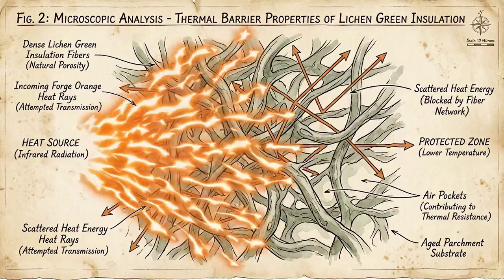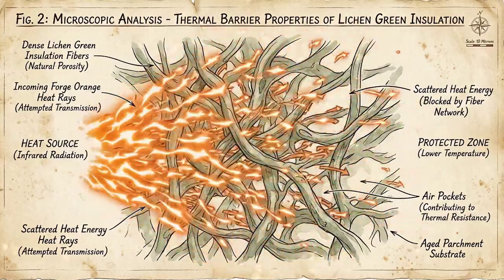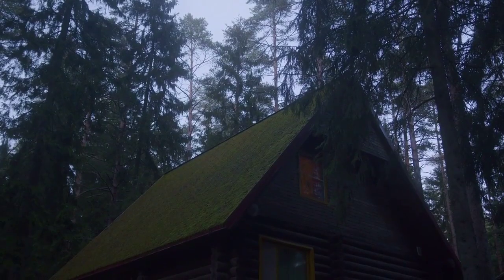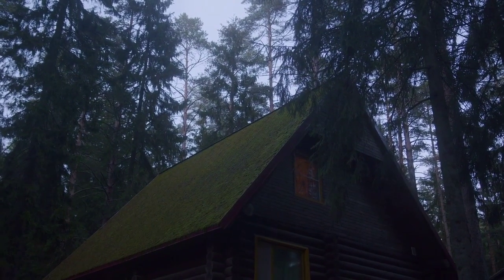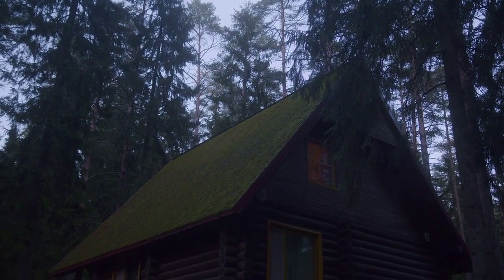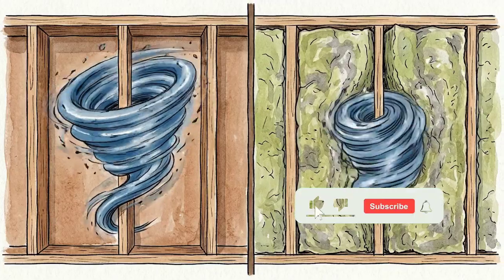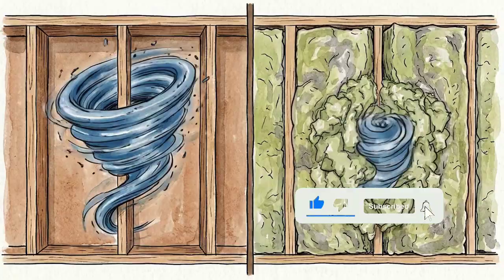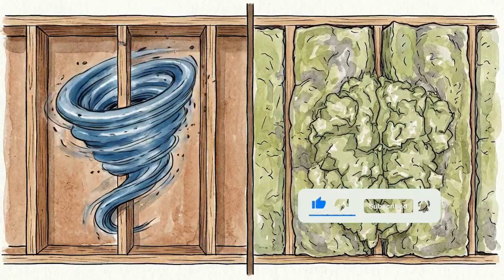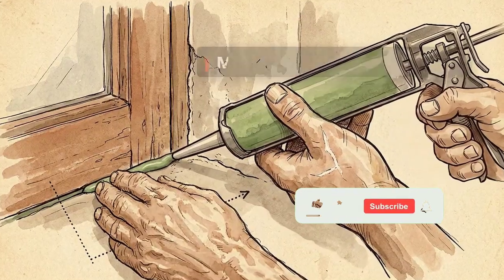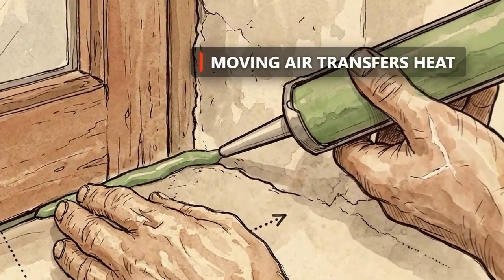Insulation is designed to stop conduction and radiation. It does not stop convection through the cavity itself. The cold spot is a symptom of air movement, not insulation absence. Adding insulation to a leaking cavity reduces the cold spot marginally. Sealing the air leak eliminates it.